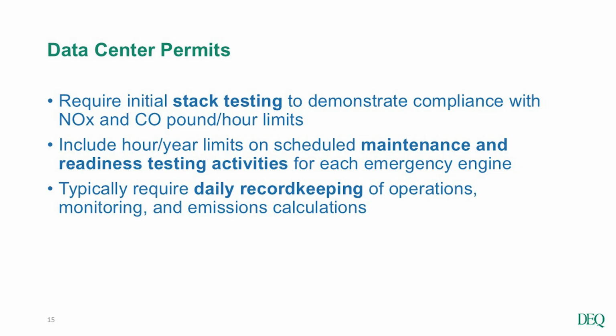We do include hours-per-year limitations on maintenance and readiness testing activity. Over 10 or 15 years of experience with some of the older data centers, we've found that most of their actual emissions occur from the maintenance and readiness testing — things happening 15 minutes a week, an hour a month, at certain durations — whereas it's somewhat rare that there's an actual loss of power resulting in the genset operating for a true emergency event. That does happen, but most emissions come from maintenance and readiness testing.